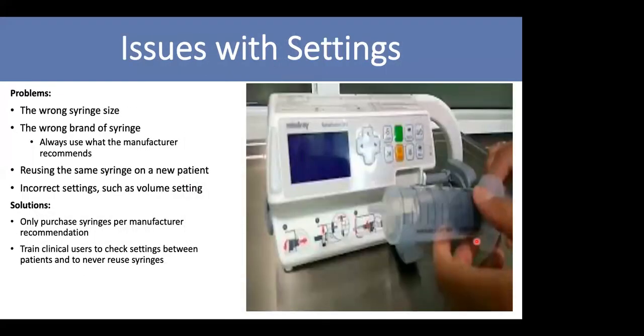Issues with settings are where you're always going to see alarm errors. The wrong syringe size is one. If the wrong brand or type of syringe that the manufacturer recommended is not used, you're going to get an alarm also. We have a similar problem in Malaysia too. Certain syringe pumps you need to use according to the recommendation. If you use an unknown brand because it's cheaper, it's going to give some alarm. The alarm error code will appear and show that the syringe does not match the particular syringe pump. And reusing the same syringe on a new patient, you have to stop doing that. That's the wrong thing to do.